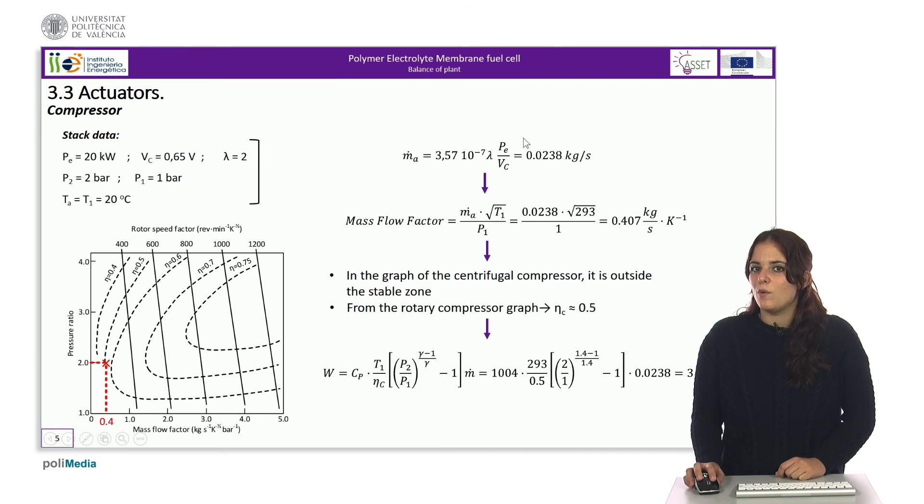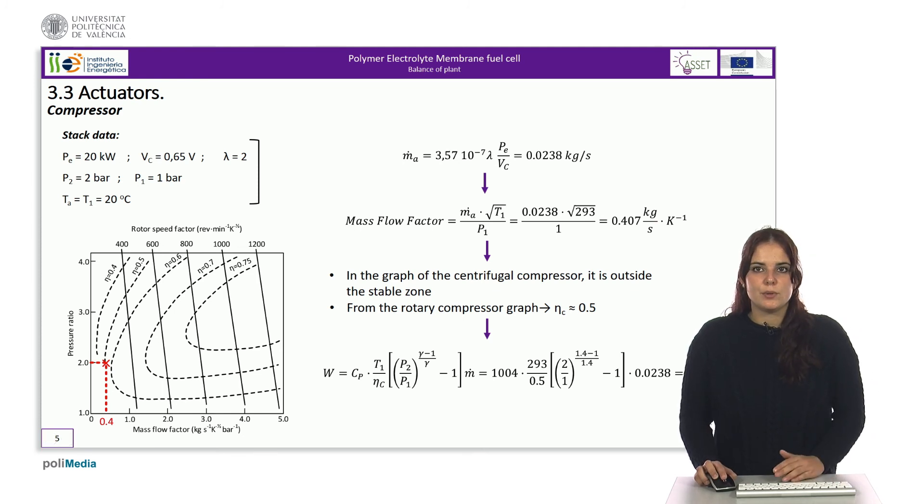With this value, the mass flow factor coefficient is calculated. Considering that the pressure ratio is 2, we check if the centrifugal compressor is viable and we see that the operating point is above the surge line.